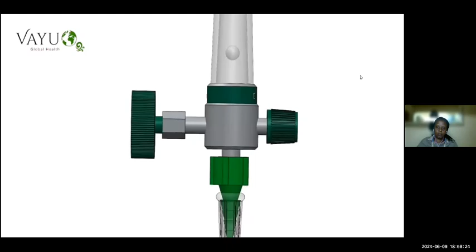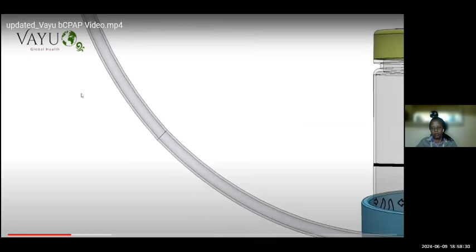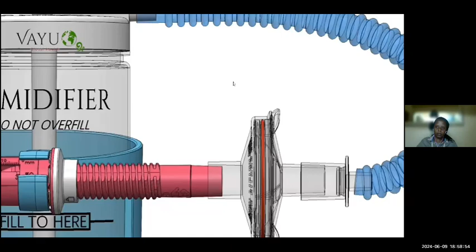The Vayu bCPAP system uses an external oxygen source, such as a wall source, oxygen cylinder, or high-pressure oxygen concentrator. From the source, oxygen tubing connects to the Vayu blender. The blender innovatively blends pure oxygen to an adjustable concentration with atmospheric air by the Venturi effect. This ensures the patient does not become hyperoxic and helps prevent consequences such as bronchopulmonary dysplasia and retinopathy of prematurity. The blended air is then filtered using a reusable filter, which removes viruses and other pathogens. The gases are then humidified in a bubble humidifier to prevent the patient's airways from drying out.